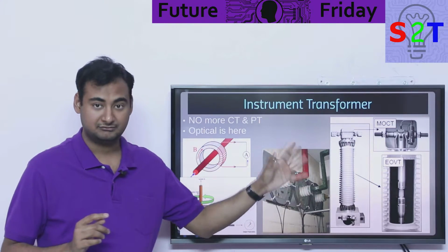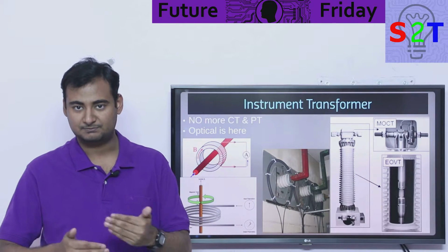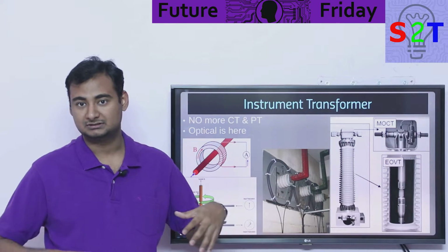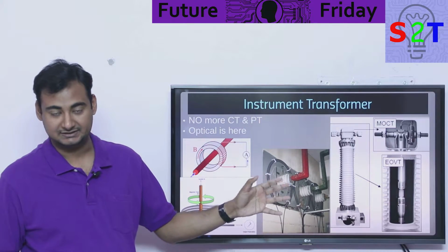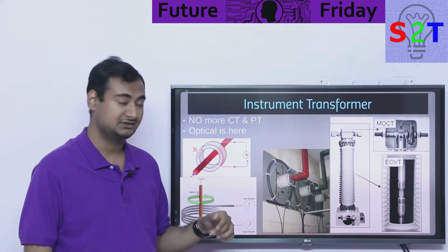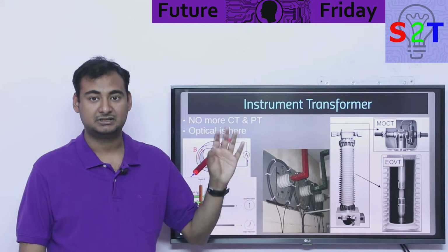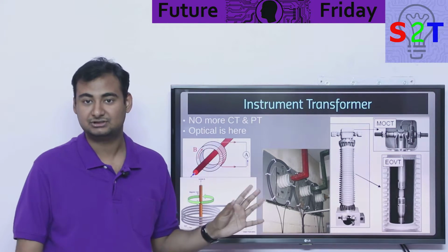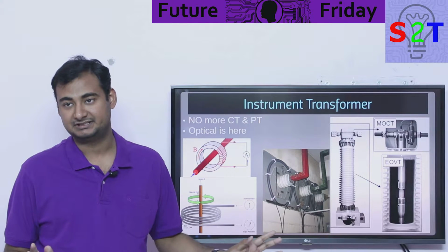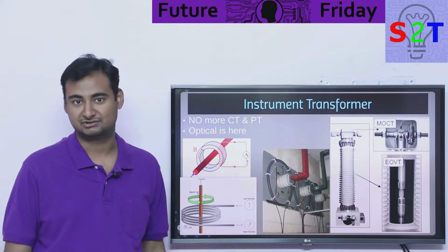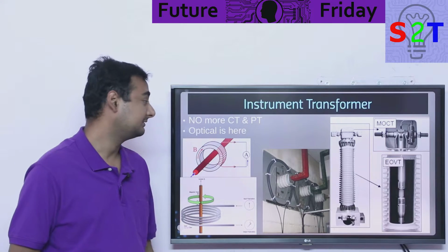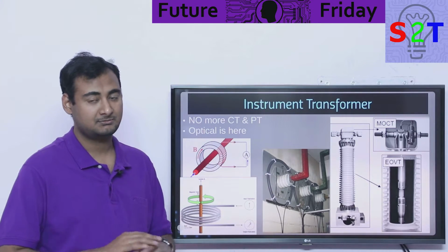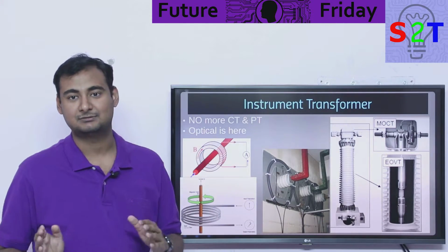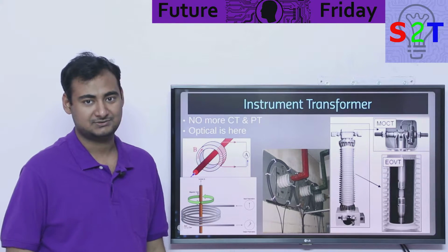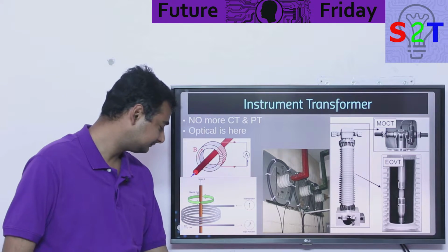These equipment are in use right now, as I've told you step by step. Many modern substations being built right now are using this as of now, as I talk to you, and these are very good - accurate, and they do the job very well. They don't have oil that explodes, they generally have nitrogen just as a suppressant. So the instrument transformer is gonna go away - I don't expect to see them in new constructions. That's how we replace the instrument transformer.